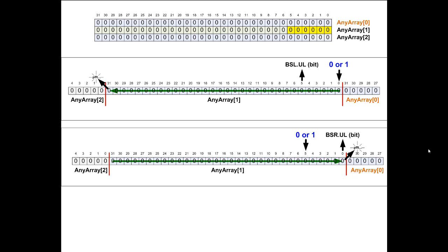And then on the bottom, you have the bit shift right. The only difference between a bit shift left and a bit shift right is the position of the unload and where new values are pulled in. So if you're going left, new values are always pulled into bit 0, and whatever the length is, in this case 6, they're unloaded at that position. But they keep on going across that double integer until they disappear when they leave bit 31.